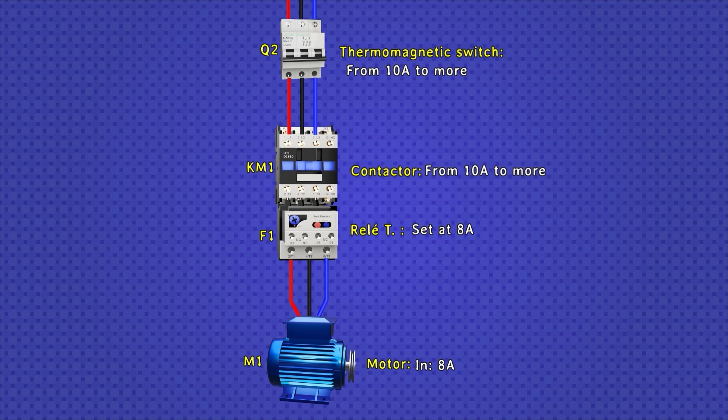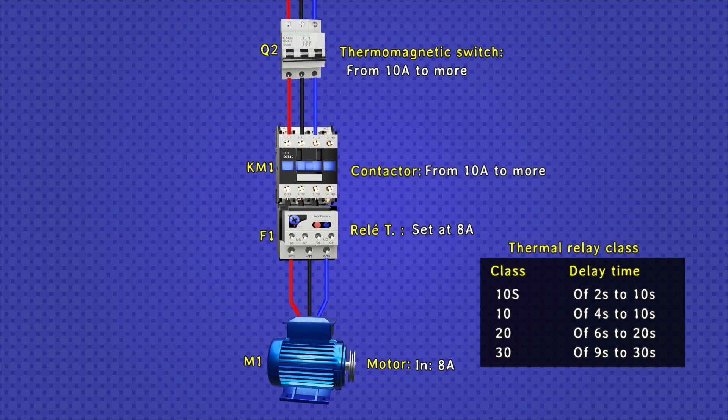Furthermore, even if the motor is changed, it can be operated with the same relay, just adjust its trip current intensity, and that's it. While the thermomagnetic one cannot, since these come with values established according to the standard, which can be 10, 16, 20, 25 amps, etc.